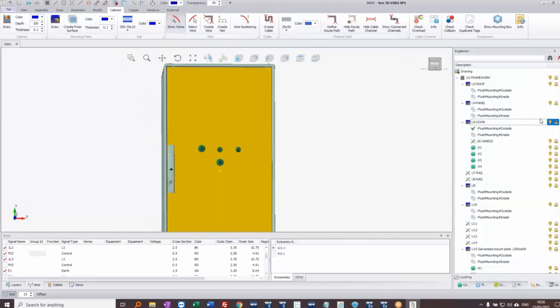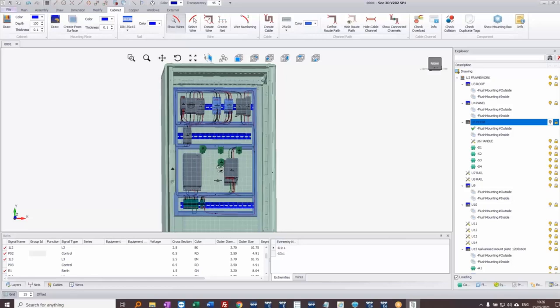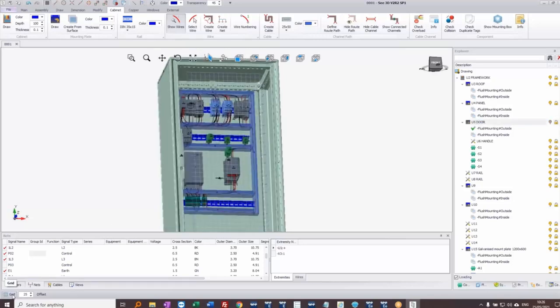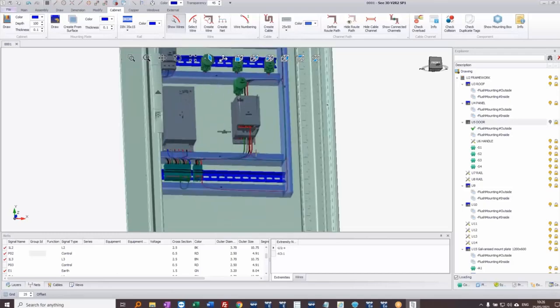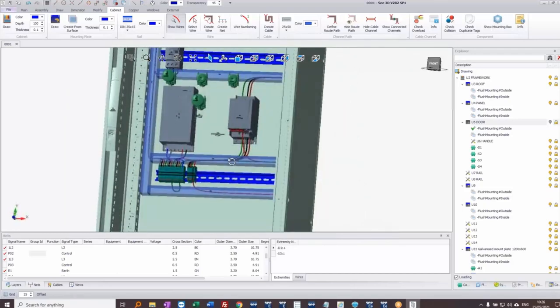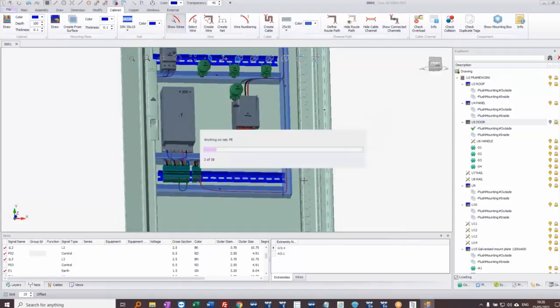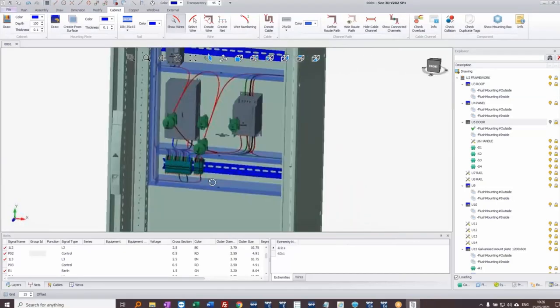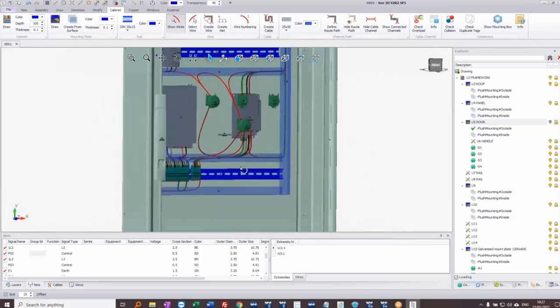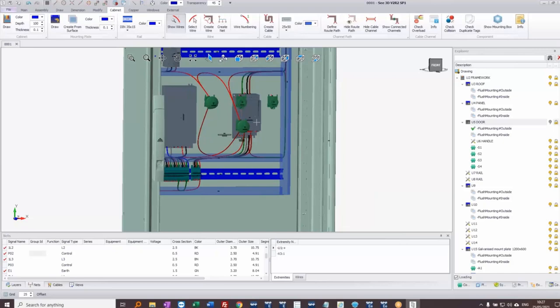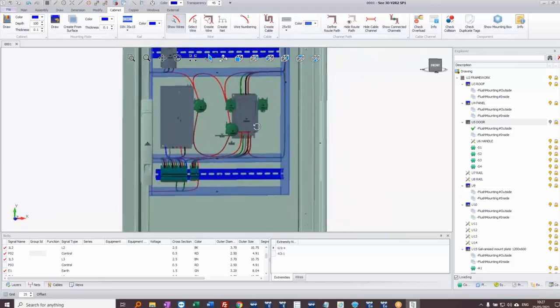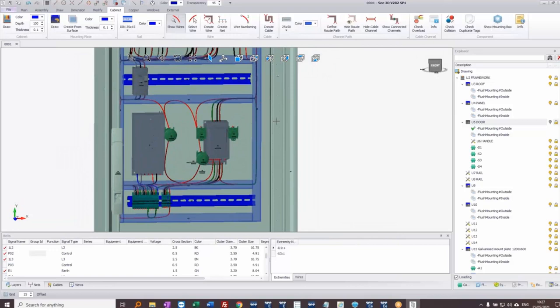If I turn off the display of the door and also turn off the grid display on the bottom left, I can see the push buttons in mid-air — mounted on the door. When I right-click and reroute all nets, it routes the wires, but they go straight from the backplate — meaning I won't be able to open the door. I need to add routing around the side to account for the hinges.